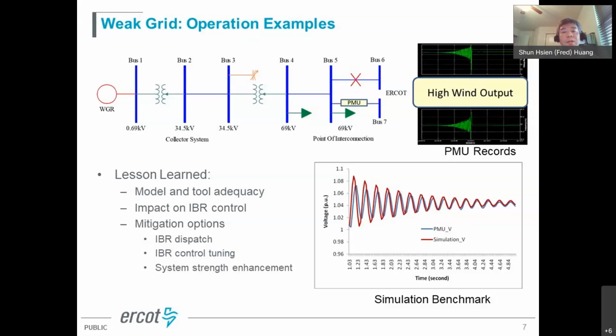As you can clearly see, under that weak grid condition, similar to what Nick, Jason, and Sebastian mentioned, because of the outage the system impedance increased. So the controller, originally adequate for normal system conditions, became too aggressive. Under high wind output, we started seeing undamped and even negatively damped oscillations, and eventually the wind project tripped. It tripped several times before we began investigating, and this weak grid issue really helped us gain a lot of lessons learned from these examples back in early 2012, 2013.